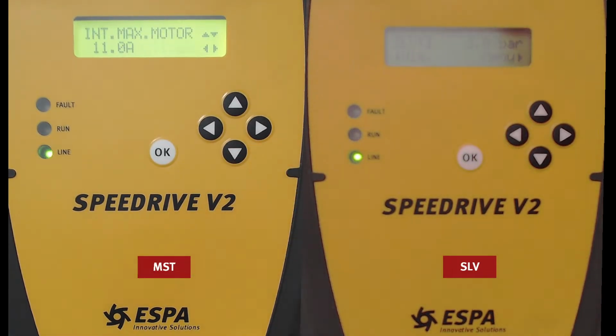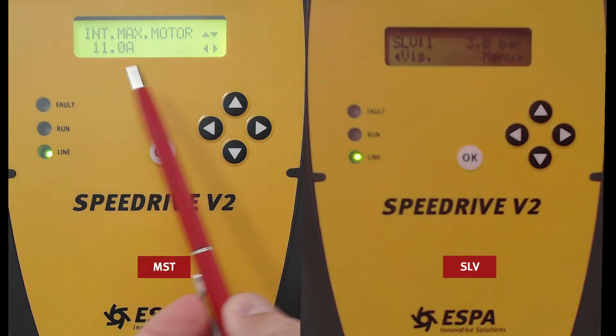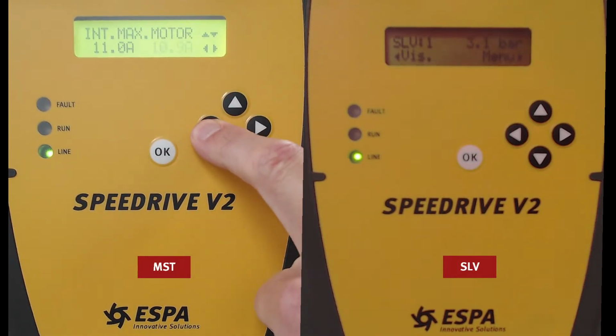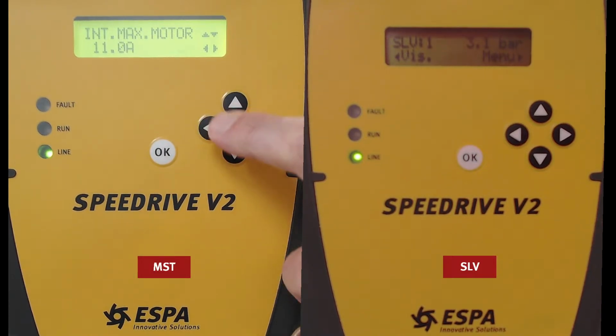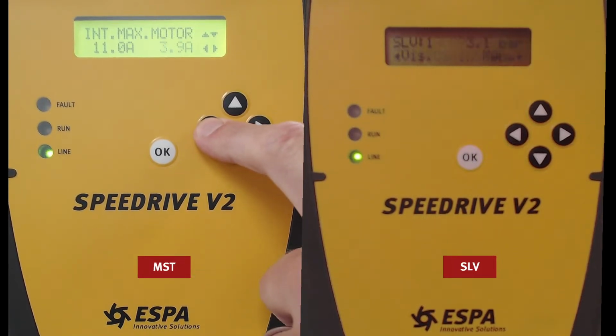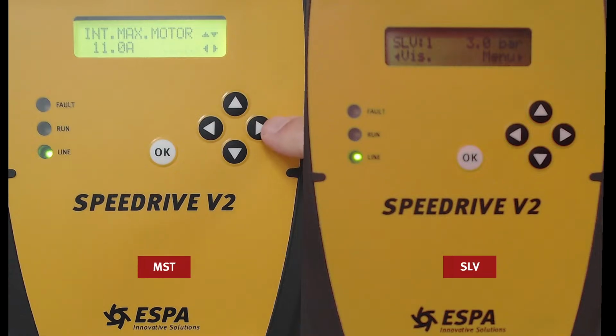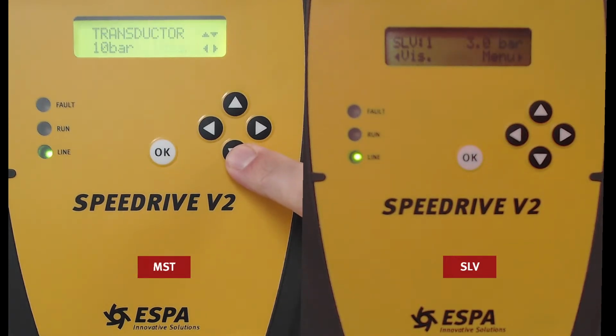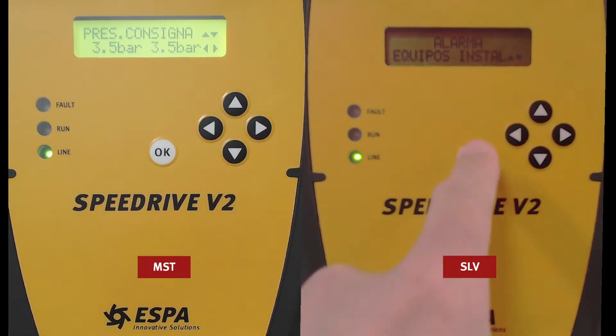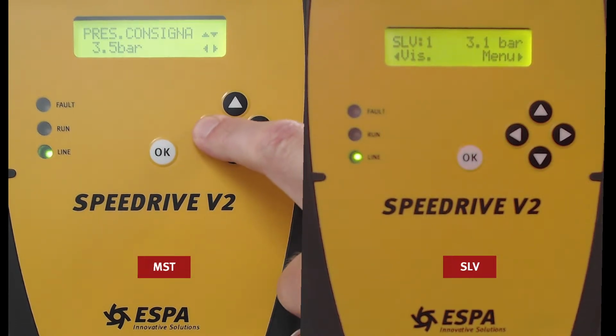Let's continue. Maximum current of the motor, or maximum intensity, 11 amperes. This is also found on the plate of the motor. In this case, 11 is too high. The plate indicates 3.6, so we will set it accordingly. This is also a very important parameter because it will prevent the motor from going over the maximum current. Press OK. Save it. Let's continue. Transducer 10 bar. This is okay. We can use a transducer of 16 or 25 bar just for pumps that give more than 100 meters of head. We will leave it at 10, as it was. 3.5 bar duty point, we can leave it at 3 as before.